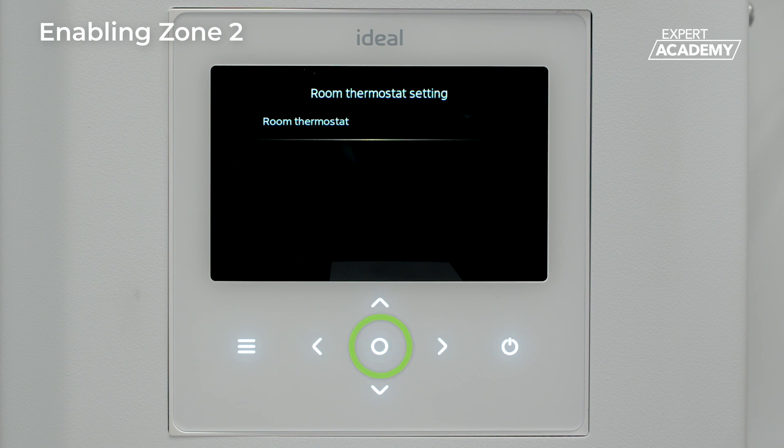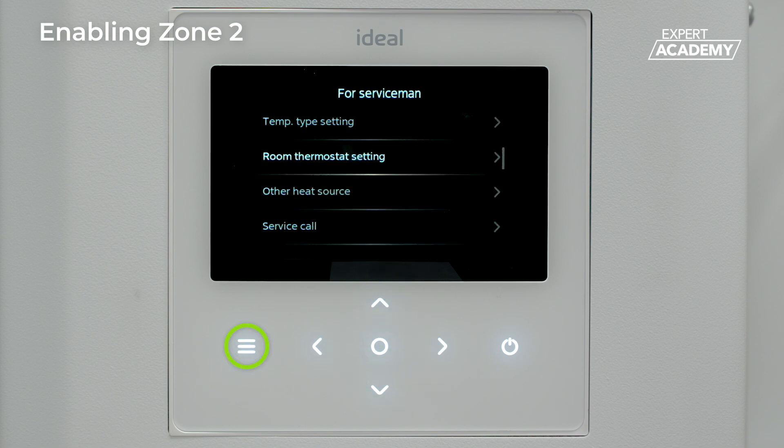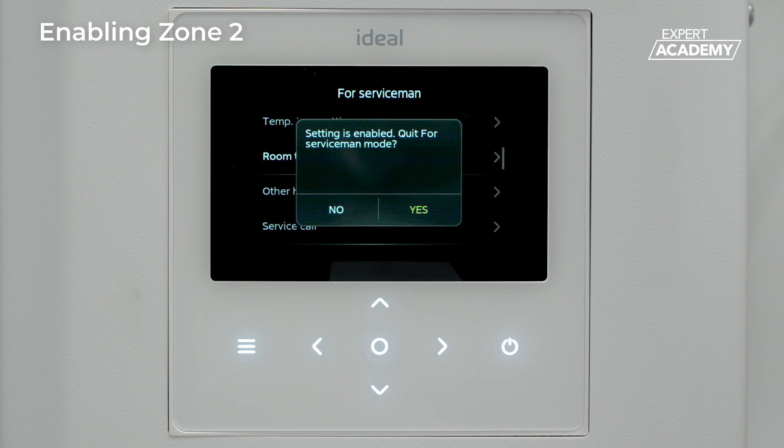Click enter on room thermostat and use the arrow to select the double zone option. Once selected, press the menu button repeatedly to exit the for serviceman menu. A pop-up window will appear stating the setting is enabled. Select yes to save.